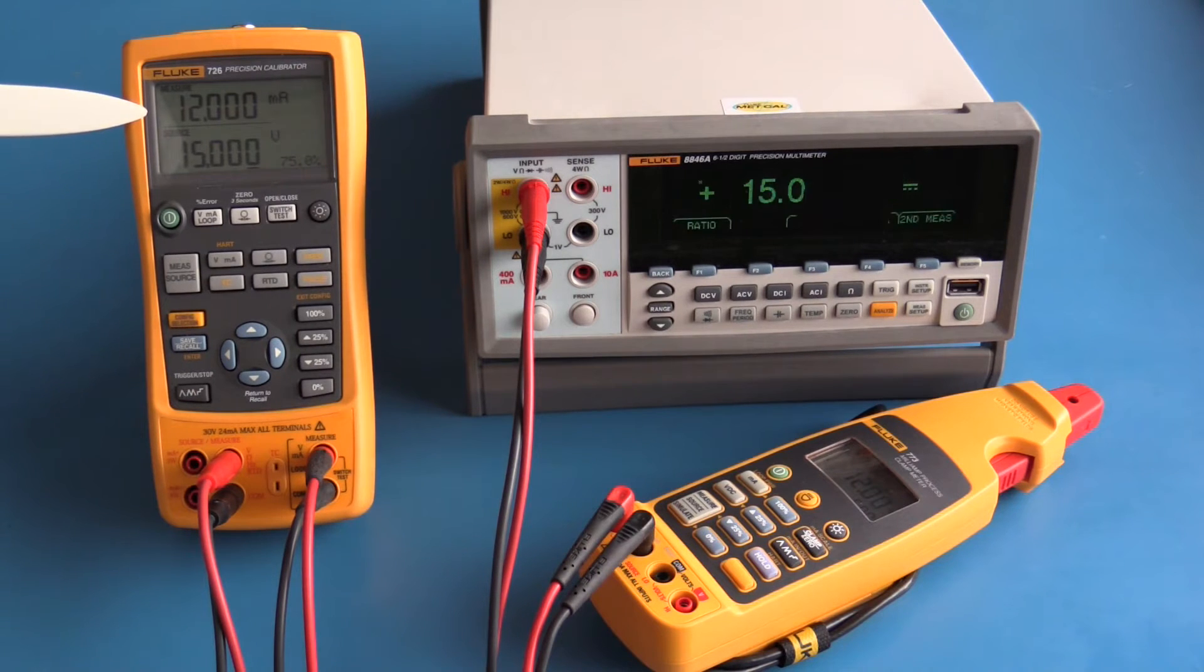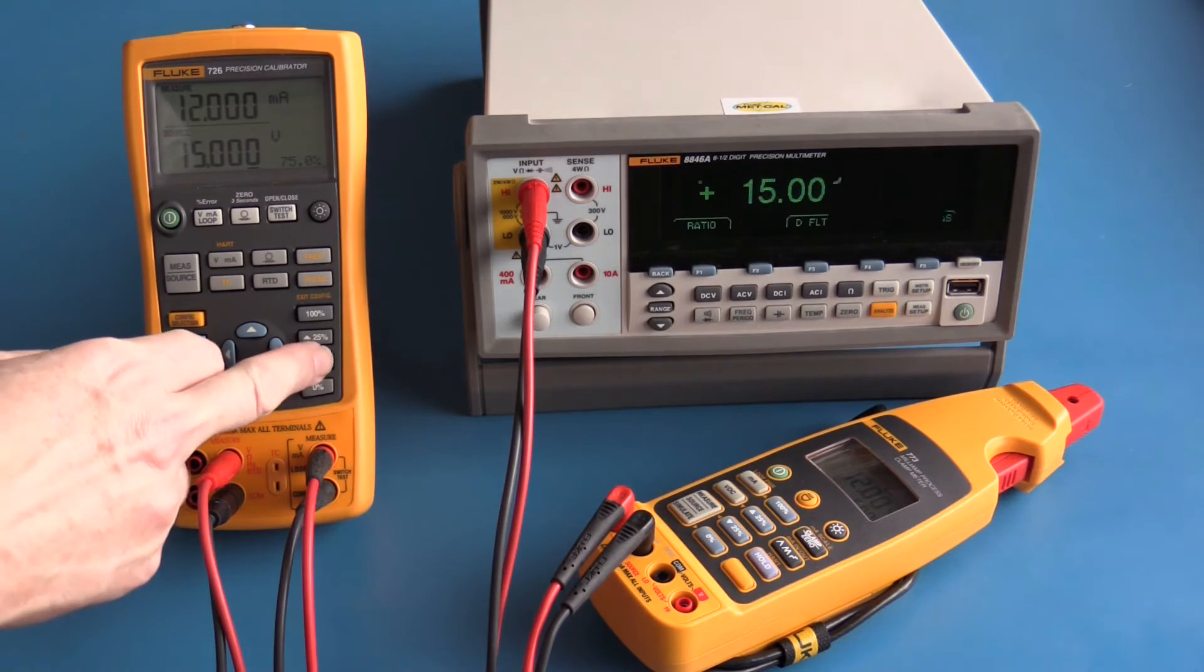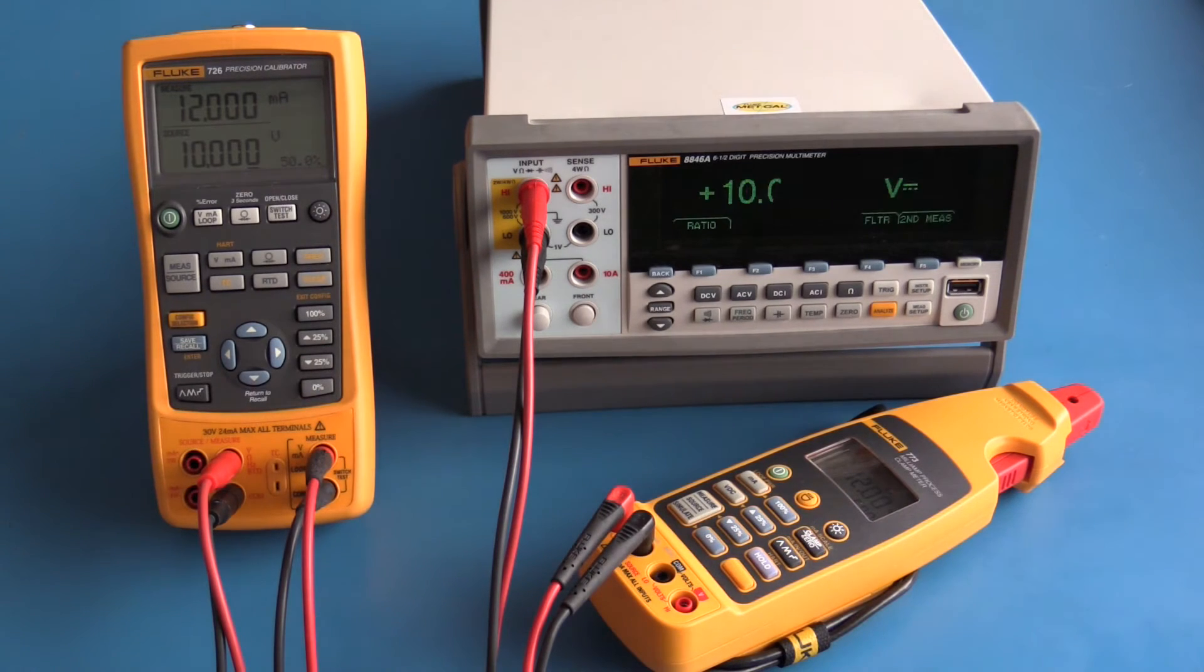The Fluke 726 is able to source up to 20 volts. It can also power a 24 volt transmitter. To change the voltage being sourced, I can go up and down in 25 percent steps. So that's 10 volts, for example. You can see we're reading pretty close to 10 volts on the Fluke 8846a within the allowable range.